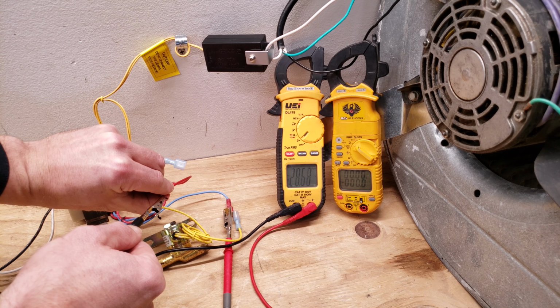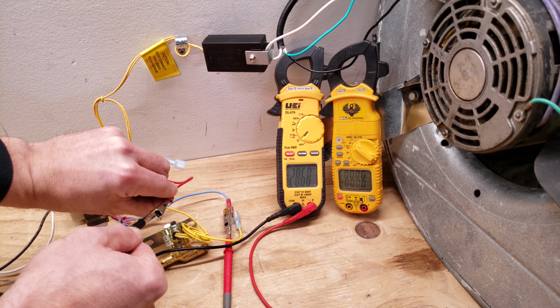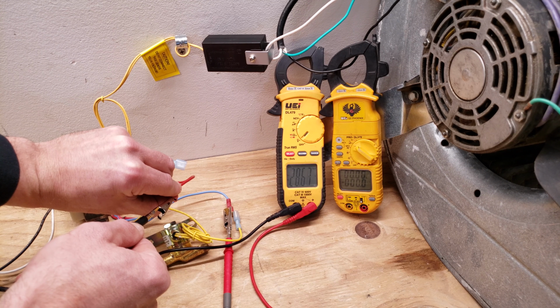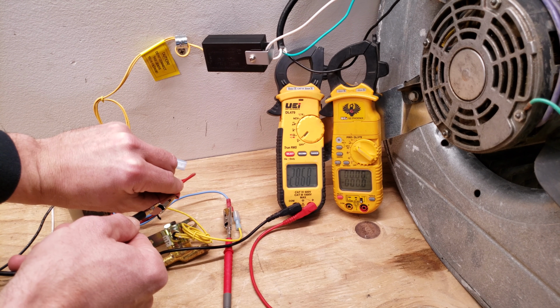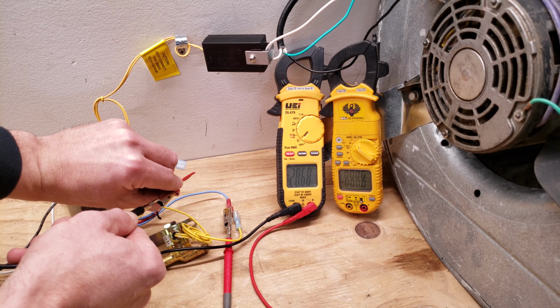It's just not going through the relay right now. So you see it's reading 28.67 volts, so you're going to normally have anywhere from say 24 to 29 volts coming out of the transformer.